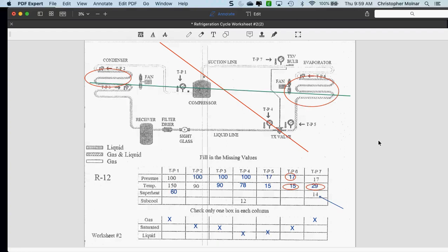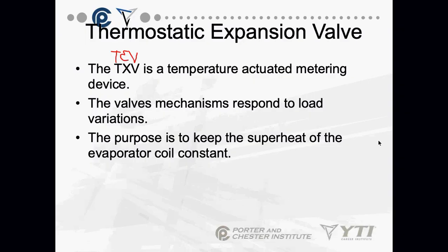The refrigerant isn't boiling off? Which would do what? You're on the right track. It'll introduce liquid refrigerant into the compressor. That's exactly right. I've got to have a little bit of superheat. Superheat is my sole protection against liquid refrigerant into my compressor. Okay. So, back to this.